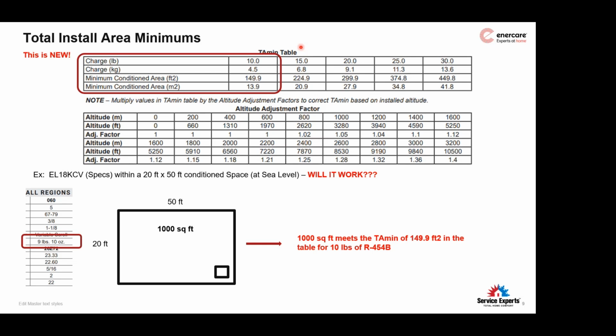Anyway, the whole point of this table is that there is an area minimum now. In the event that the entire refrigerant charge dumps into that space, it needs to have a minimum conditioned area of about 150 square feet.